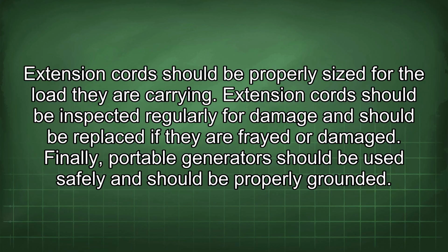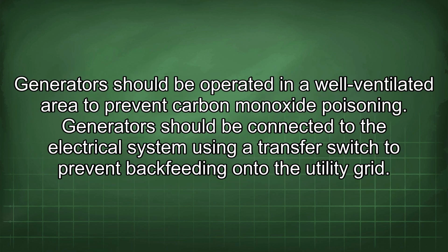Finally, portable generators should be used safely and should be properly grounded. Generators should be operated in a well-ventilated area to prevent carbon monoxide poisoning. Generators should be connected to the electrical system using a transfer switch to prevent backfeeding onto the utility grid.